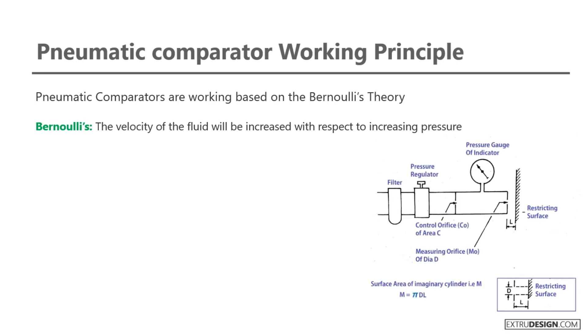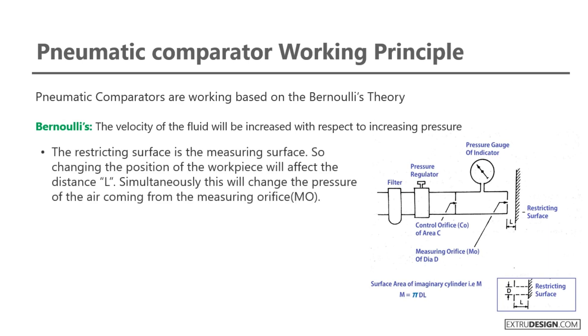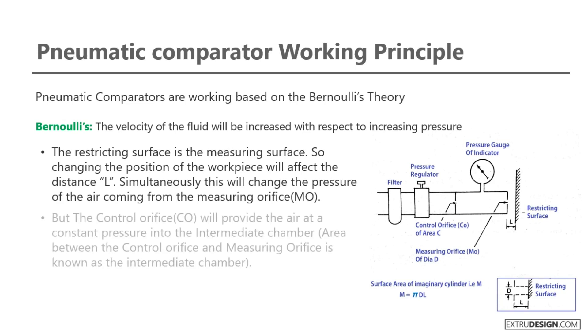Check the schematic diagram of the pneumatic comparator. The restricting surface is the measuring surface, so changing the position of the workpiece will affect the distance L, thereby changing the pressure of the air coming from the measuring orifice. The control orifice provides air at a constant pressure into the intermediate chamber. The intermediate chamber is the area between the control orifice and the measuring orifice.